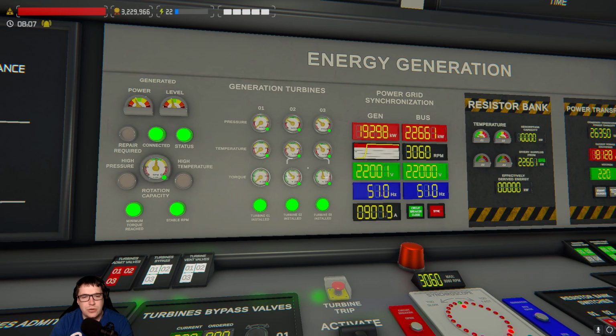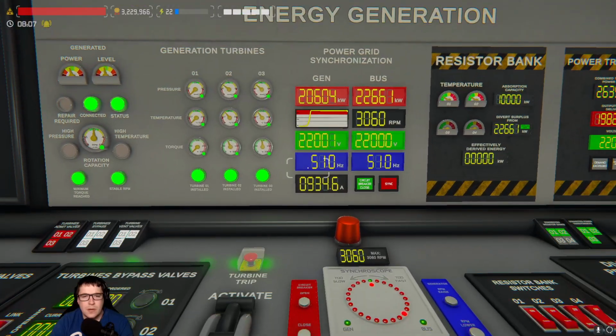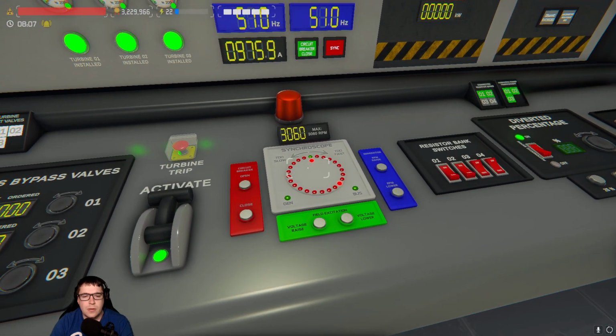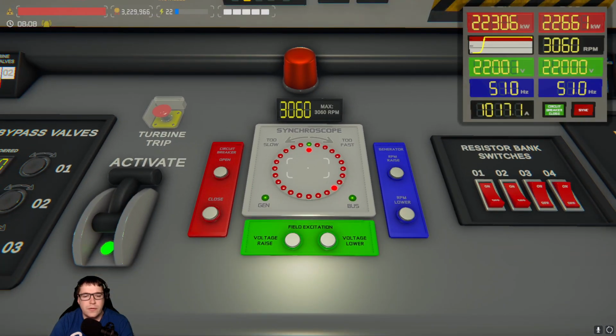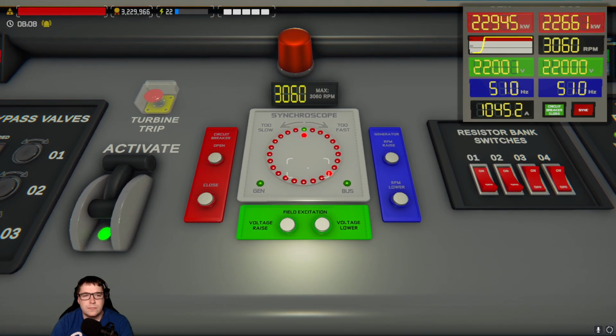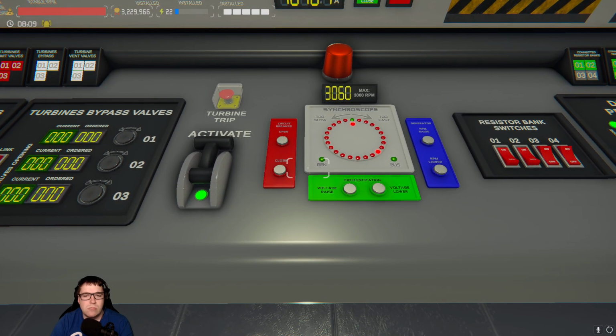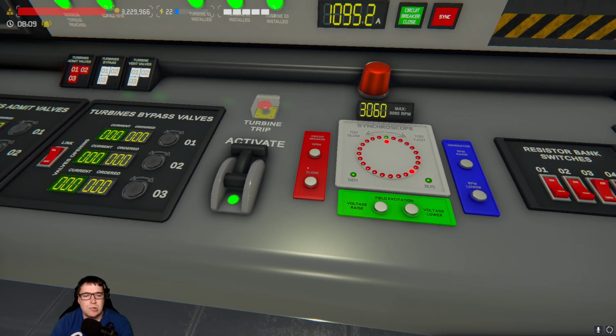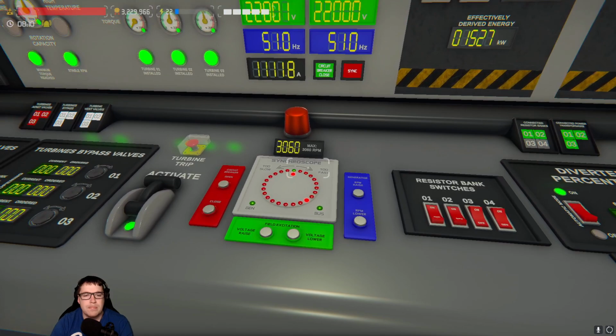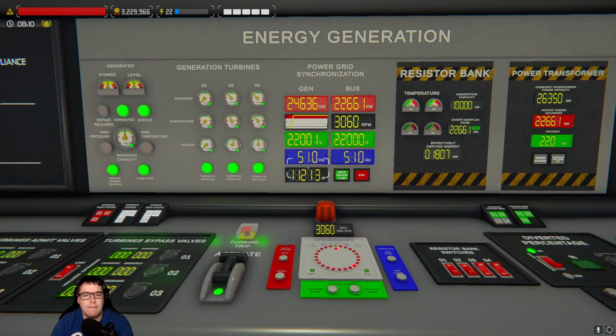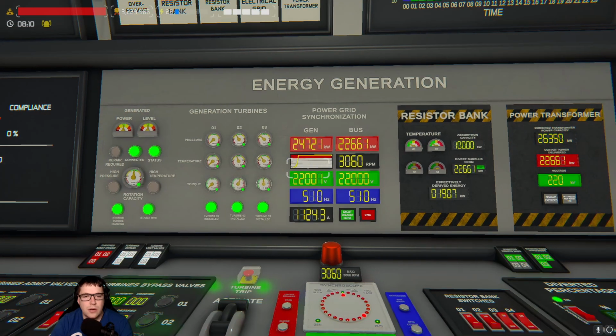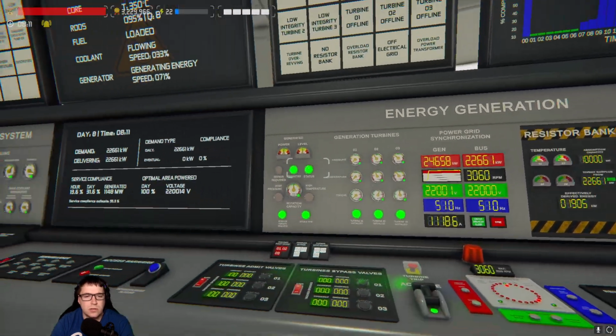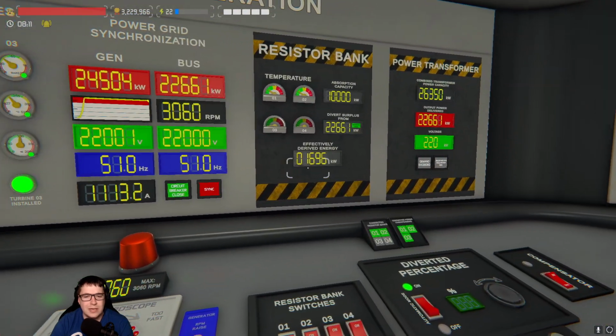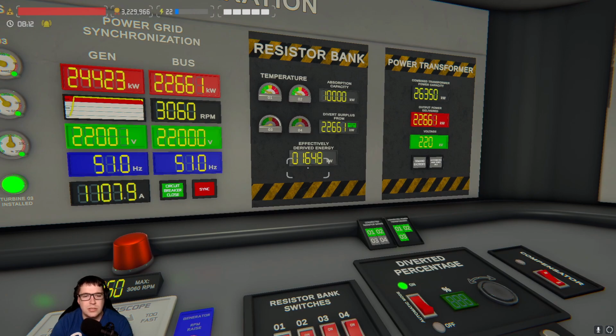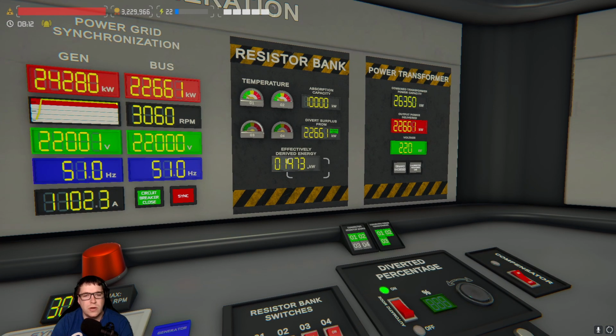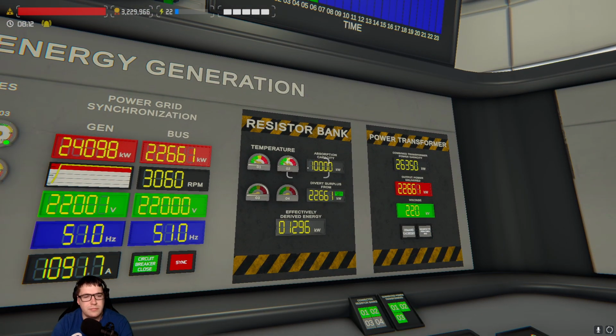So generator 2 is now being brought online. So what we'll do is over here, we don't want to do that one. Right, so as you can see now, we are over what the system is asking. So that automatically now has shifted the difference onto the resistor bank. So we are currently 1,600 kilowatts over. Obviously well within the 10,000 kilowatts, so that's fine, that is manageable.